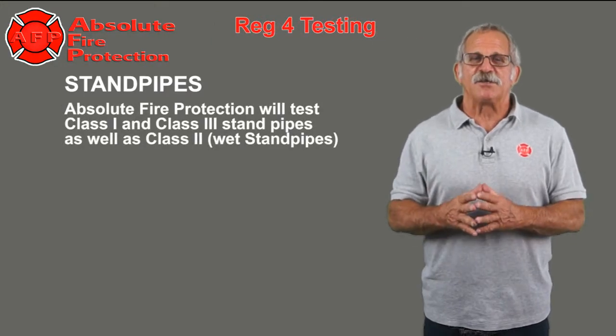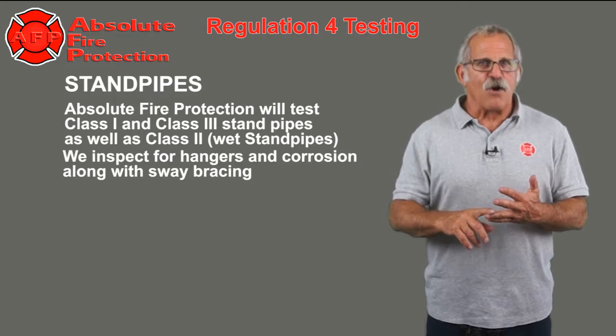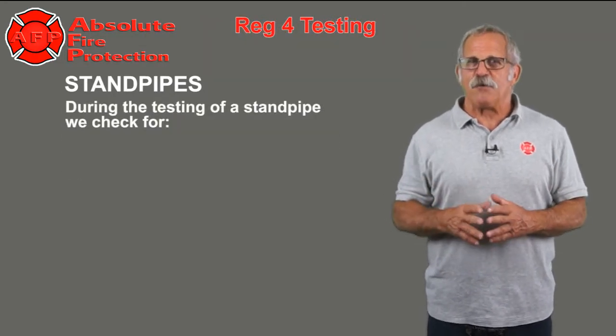Absolute Fire Protection will test Class I and Class III standpipes as well as Class II wet standpipes. We inspect for hangers and corrosion along with sway bracing. During the testing of a standpipe, we check for air tests, hydrostatic tests, and flow tests.